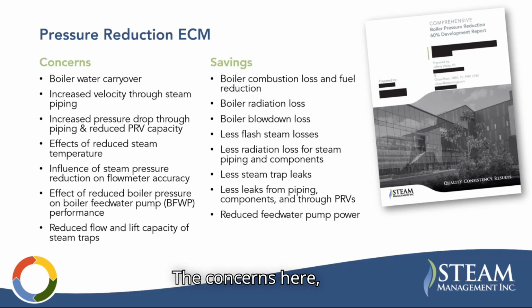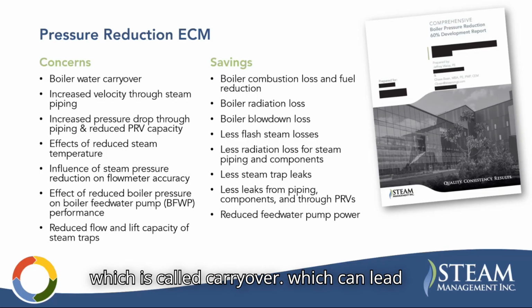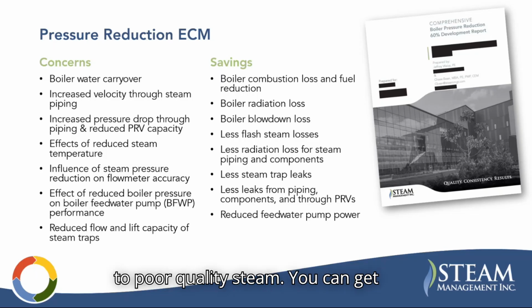The concerns here: boiler water carryover. Increased velocity out of the boiler can lead to entrainment of the boiler water escaping into the steam system, which is called carryover, which can lead to poor quality steam. In an autoclave or something, you can get spots on the instruments that are being cleaned and things like that. It can also just lead to erosion and damage of the piping.